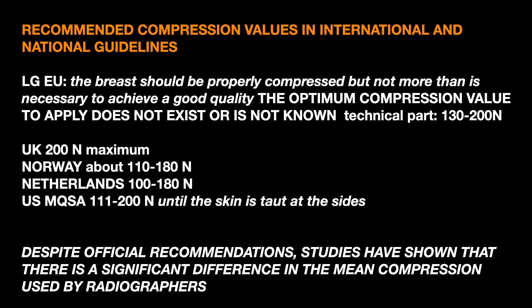It has to be then also a maximum value of the compression force to apply. However, there are no recommended compression values in European guidelines. Apart from a purely qualitative description, it is even emphasised that the optimal value of force to be applied does not exist, or at least is not known. In the technical part of the guidelines, we read a range from 130 to 200 N.